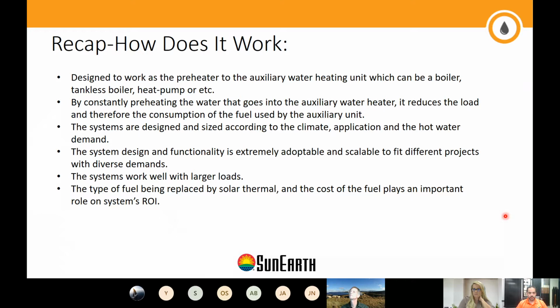Once you introduce the solar thermal into this equation, it's continuously preheating the water before it goes to the main heater. For example, if you have your main heater set at 140 degrees Fahrenheit and you're feeding it water at 140 degrees, the heater will not kick on or start operating. It will only start operating if it begins receiving water at lower temperatures.